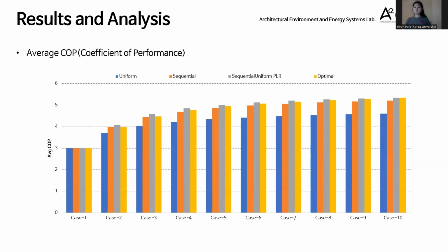The following are the research results. Case 1 to 10 represent the number of chillers present in the building. For example, case 4 indicates that 4 chillers are responsible for the building's cooling load, while case 6 means that 6 chillers handle the cooling load. The chart below represents the average coefficient of performance, COP, and the conventional case with only one chiller is labeled as case 1.